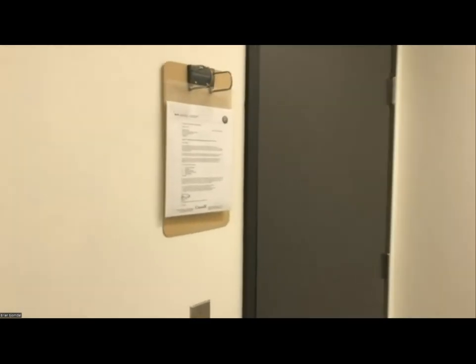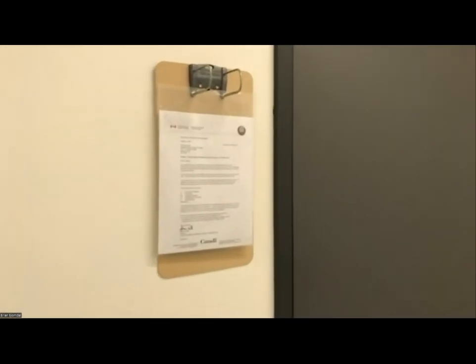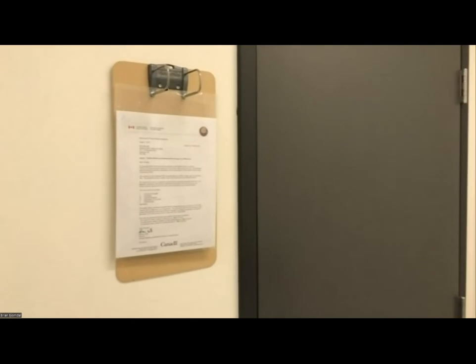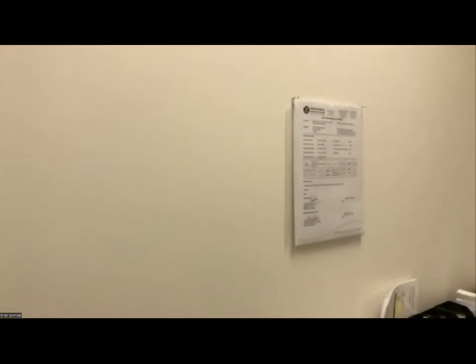This is a licensed facility where we have a calibration license with the CNSC, and it's posted inside the lab here. Because it's a sealed source, we also have to do annual sealed source leak testing, and we post that in the lab as well, together with any specific information on the source that we use, because we use a cesium-137 calibration source. So it's a fairly straightforward setup.